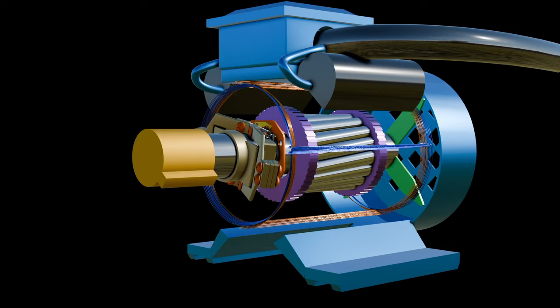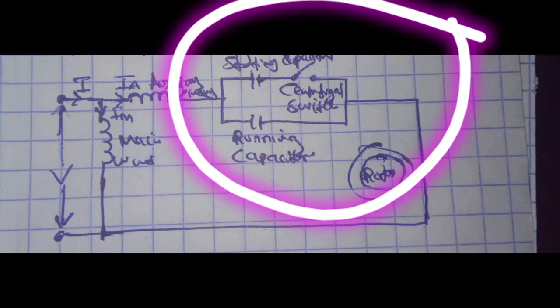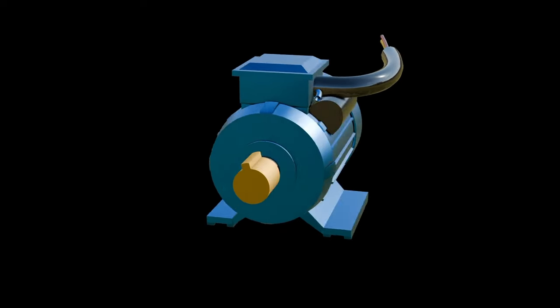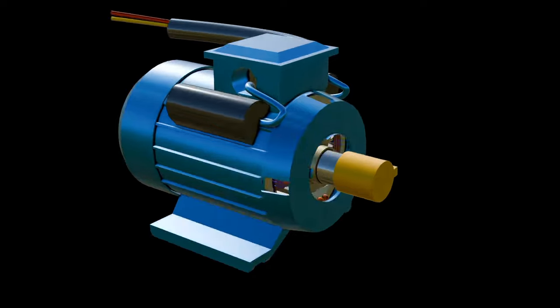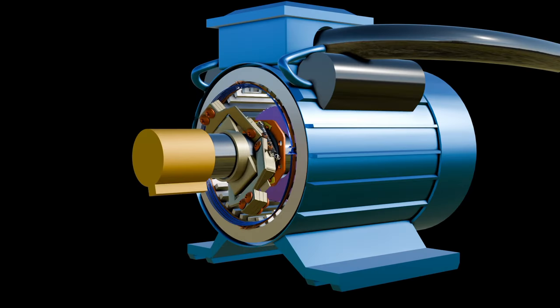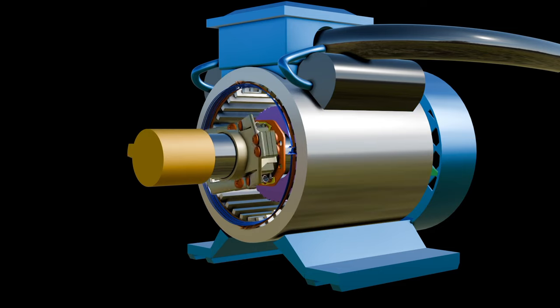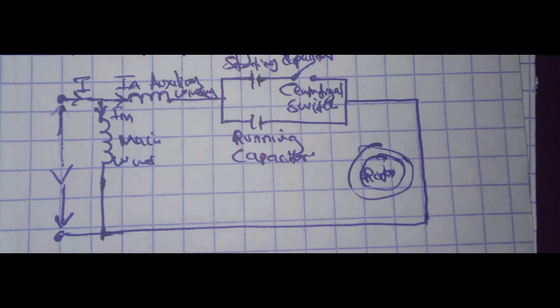Capacitor start, capacitor run induction motor: In this type of motor, two capacitors are connected in parallel with series in auxiliary winding. Out of these two capacitors, one capacitor is used only for starting and another capacitor is connected permanently with the motor for running. The starting capacitor has high capacitance value and running capacitor has low capacitance value. The starting capacitor is connected in series with a centrifugal switch that will open when the speed of the motor is 70% of synchronous speed.